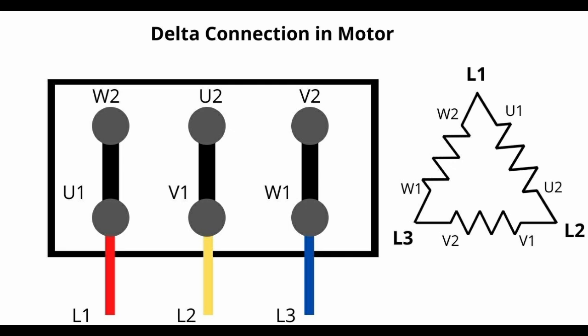make sure power is isolated. Winding resistance can be checked using a multimeter between terminals U1, V1, and W1.